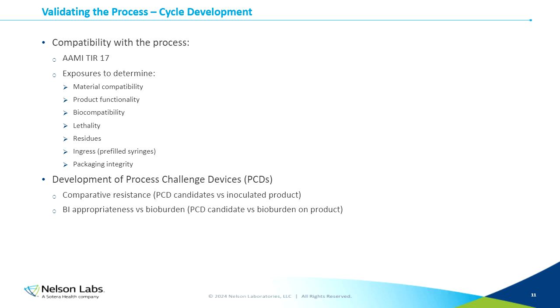Another thing that we can do with exposures is look at biocompatibility. Now, I'm not going to get into the details of biocompatibility. That will be discussed in subsequent days. But that's another thing where we can expose product and then evaluate the biocompatibility of the process. One thing that's very important is, can we achieve the lethality that we need to achieve with the process? So we can actually look at lethality. We can perform fractional cycle exposures and monitor that product with appropriate microorganisms, often in the form of a biological indicator, to make sure that we're able to achieve the lethality we need to achieve for the product. Residues is another item that we can look at by performing exposures with the product. We will talk about residues in subsequent days of this series. So I'm not going to get into the details here.